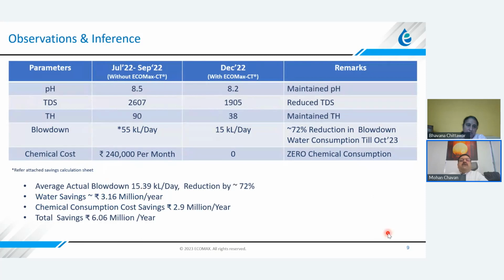This one is the economics, before and after case. So pH was maintained without and with, so 8.5 to 8.2. TDS is 2600 to about 1900. Total hardness, 90 to 38. Blowdown 55 meter cube per day to 15 meter cube per day. So there is almost 70+% reduction in the blowdown water consumption.